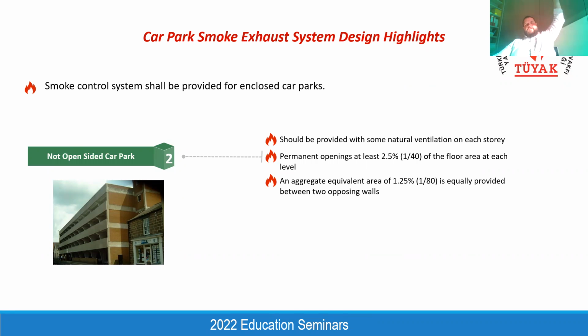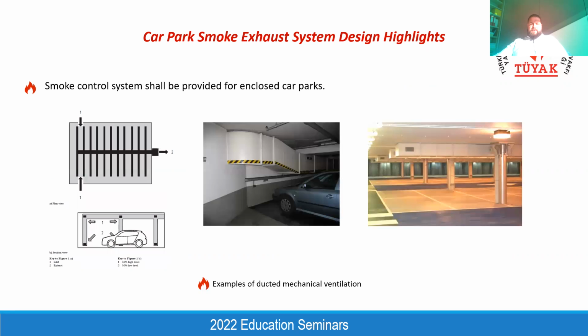It is not possible for the basement floor car parks, but if you are designing a car park for the airport terminal building, for example, the car park of the new Istanbul airport is considered open car park, and we don't have a sprinkler system and we don't have a smoke control. But it's really difficult for enclosed car park located beneath the buildings on the basement floor. And if you have an enclosed car park system, you have two options. First of all is conventional hard ducted smoke exhaust system. And the second option is a jet fan smoke exhaust system.